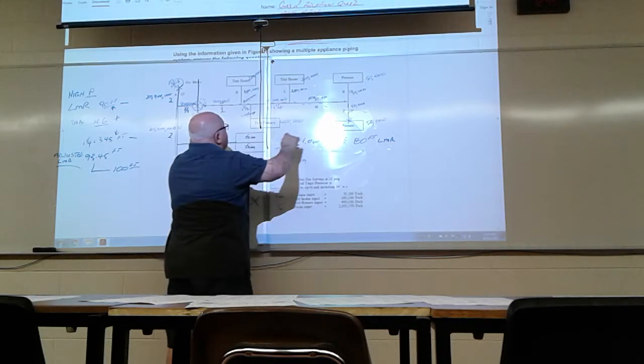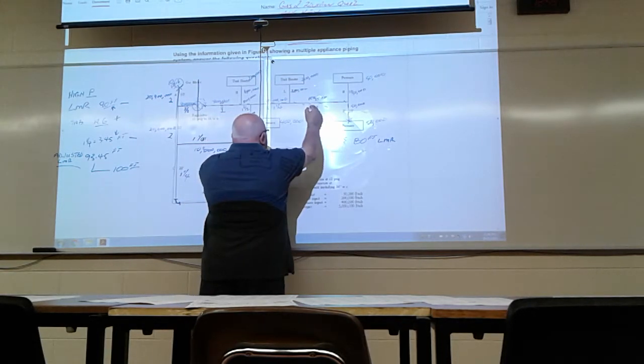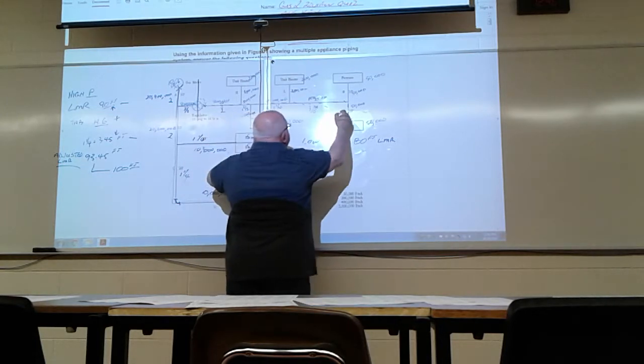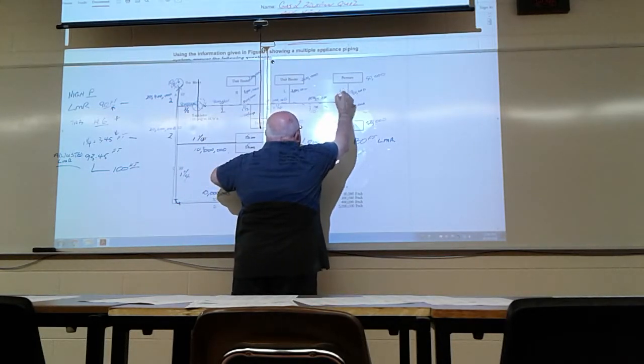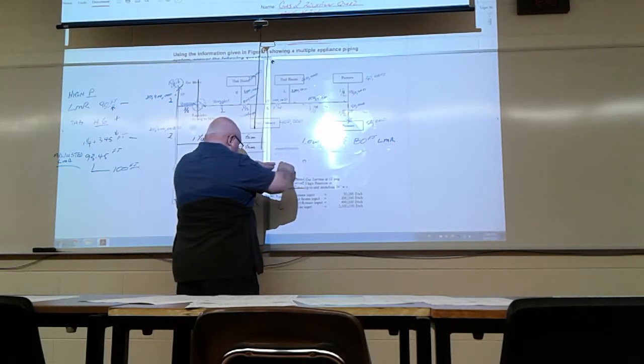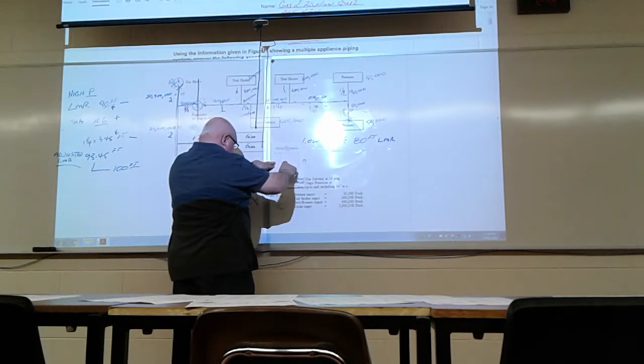Okay, 300,000 BTUs, 1.25 inches. 100,000 BTUs, 3/4 and 50,000 BTUs, ½ inch. Okay, unit heaters are 200,000 BTUs apiece, so they're going to be 1 inch and 1 inch. Duct furnace, 400,000 BTUs, 1.25 inches.